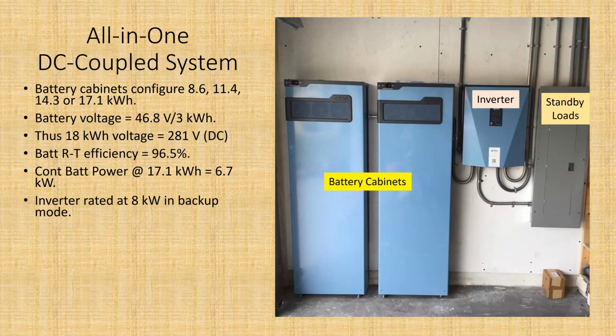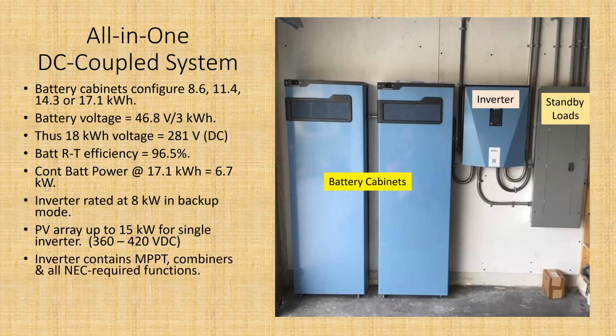In backup mode, the inverter can kick out 8,000 watts, okay? Again, here's your motor start thing. For a single inverter, you can have the array up to 15 kW. And that single inverter is rated at, well, here's the ratings on it, 8 kW. And it has all the functions. Everything required by the National Electrical Code is right inside that inverter box. I don't even think I could type this out on a piece of paper and cram it into that small box, but it's an amazing piece of equipment. The biggest piece of equipment being the standby load panel.